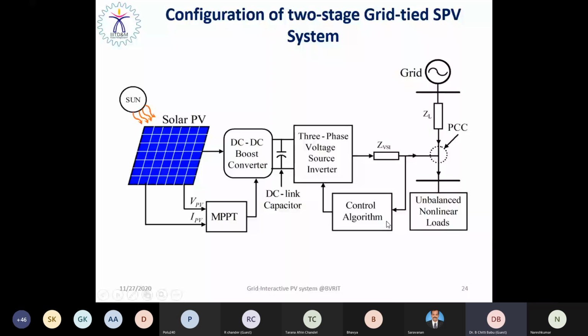According to the topology, basically 95% of grid-connected solar PV systems use the two-stage configuration. Two-stage grid-tied means it has two converters, with a DC link between them. The first is called a DC to DC boost converter. It converts our uncontrollable DC into controllable DC by boosting the solar PV voltage to a high voltage level, which is then available at the DC link, right? The DC to DC boost converter always interacts with the solar PV. This is what is called the source side converter, as it transfers power from solar PV to the DC link. Moreover, this is responsible for maximum power point tracking, as it has low conversion efficiency.